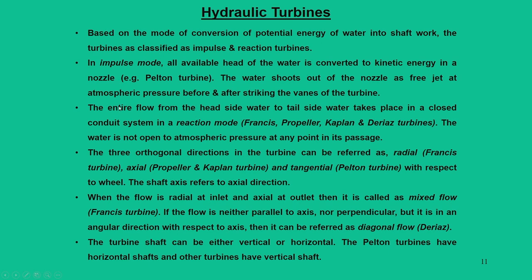Now, another way of looking at it: when the entire head available in the reservoir is used to pass through a closed conduit, then it works in reaction mode. In this reaction mode a controlled pressure difference is maintained, and the water is simply guided to strike on the blade. So, there is no conversion of the potential energy to kinetic energy in between. That is called the reaction mode. We will explain these impulse and reaction concepts subsequently.